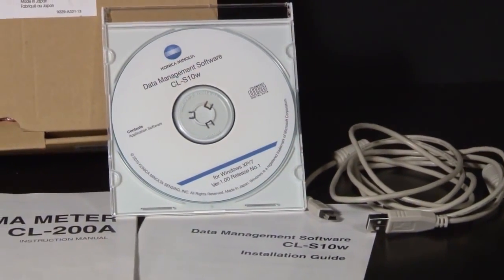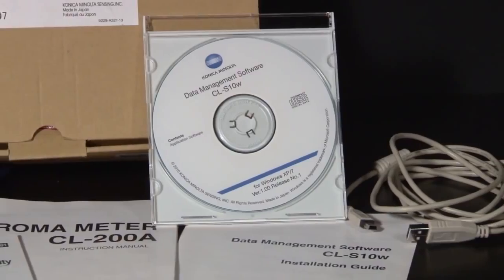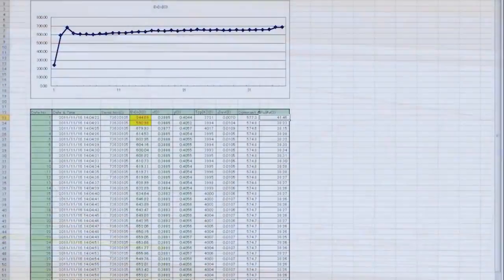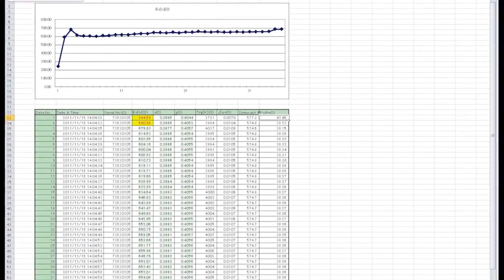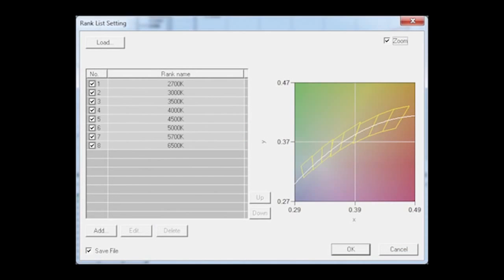The included CL-S10w software, an Excel add-on, allows easy and convenient measurement data to be transferred directly into an Excel spreadsheet. This software includes an LED ranking function that allows users to rank measurements on a chromaticity chart for easy comparison. Correlated color temperature is defined by CIE standards and plotted as an image.